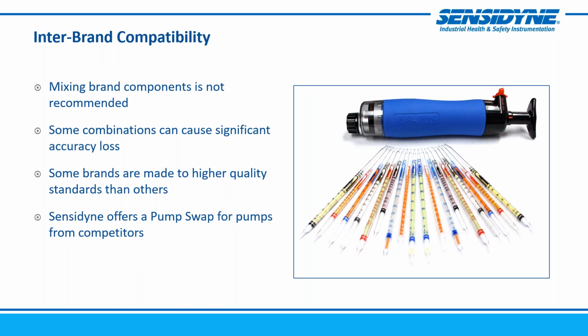So I want to talk about inter-brand compatibility. This is a common topic that does come up. Mixing brand components is not recommended. When the gas detector tubes are calibrated and go through a quality assurance protocol, they are calibrated using the specific hand pumps they are meant for within the brand. So people ask, can I use your gas detector tube in a Draeger hand pump? For 2 reasons, the answer is no. One, the Draeger tubes, for example, are a different diameter, and using a Sensidyne tube in a Draeger hand pump, you wouldn't necessarily get a tight seal. That could impact the air being pulled in, which could impact your flow range. So it's really recommended that you stick within a brand and use the correct manufacturer's hand pump for the detector tubes you are utilizing.